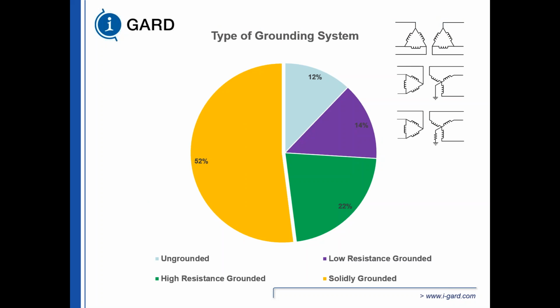So the different types of grounding systems we have in our facilities are solidly grounded, which makes up about 52% of our facilities, high resistance grounding, 22%, low resistance grounding, 14%, and ungrounded systems still account for about 12% of our facilities. And the difference is basically how we ground our source. So ungrounded systems, usually a delta transformer, delta, ungrounded systems. There's reasons why people go with ungrounded systems, although the benefits are not really that apparent. A resistance grounded system far outweighs the ungrounded system.